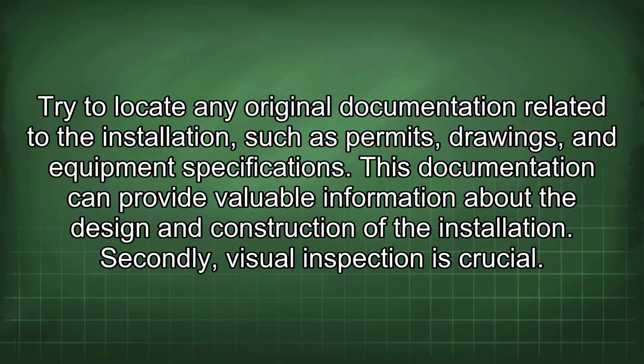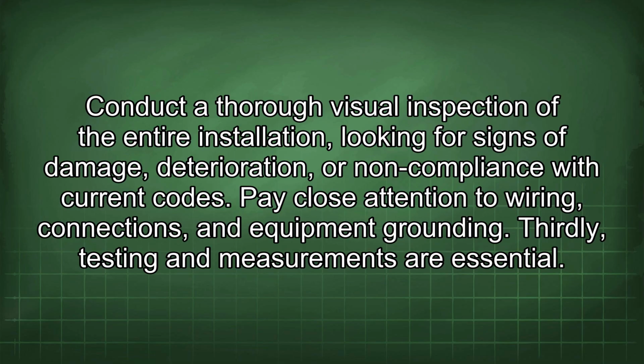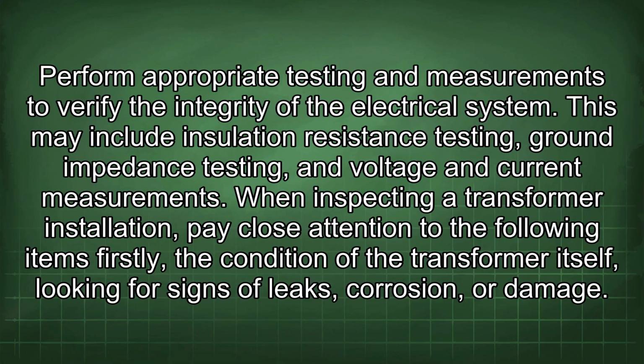Secondly, visual inspection is crucial. Conduct a thorough visual inspection of the entire installation, looking for signs of damage, deterioration, or non-compliance with current codes. Pay close attention to wiring, connections, and equipment grounding. Thirdly, testing and measurements are essential. Perform appropriate testing and measurements to verify the integrity of the electrical system. This may include insulation resistance testing, ground impedance testing, and voltage and current measurements.